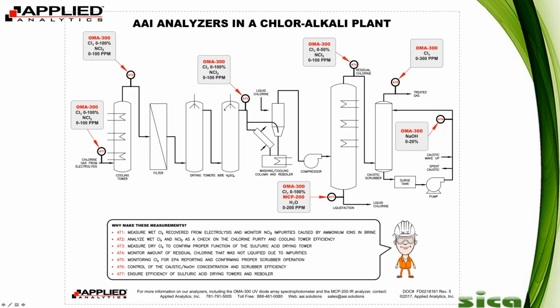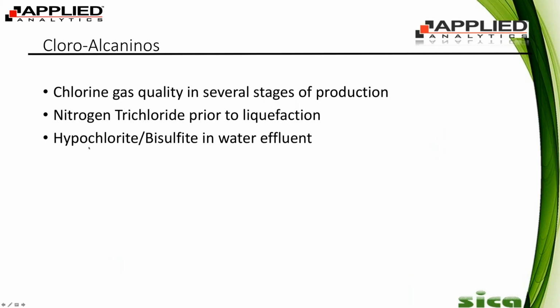And then another chlorine application would be measuring hypochlorite and bisulfite in water effluent. So a way to clean sewage water is to chlorinate it, and the way they do that is they add sodium hypochlorite. But what that does is it produces chlorine as a byproduct in the sample. So then they add bisulfite, or sodium bisulfite, to that water, which gets rid of the chlorine. So in this water treatment process, it's not quite a chlor-alkali process, but measuring hypochlorite and bisulfite are great applications for us as well.